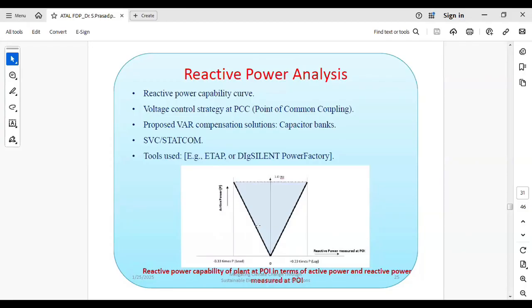The PQ capability of the PV plant: whenever you plot the PQ capability curve of the PV plant connecting to the grid at the point of interconnection, that curve has to lie outside this V curve. Then you are fulfilling the CEA requirement at the point of interconnection. If it comes inside this V, then you are violating the limit. So you have to decide what size of capacitor banks you need to connect at the PV end so that you comply with the CEA regulations.